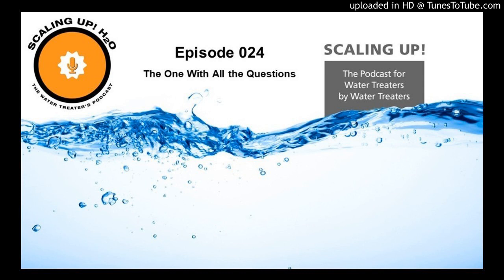So I hope that makes a little more sense on what magnetite is. Specifically, that's in a boiler in a pH environment above 10.3. It's that black, dark gray color that is just so glorious whenever you open up a boiler and you don't see any pitting, you don't see any flash rusting or anything around there, and you say, yes, not only did I do my job, the operators did their job, and here is the proof of it.